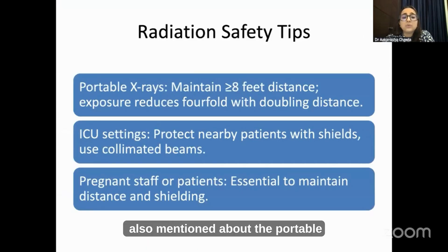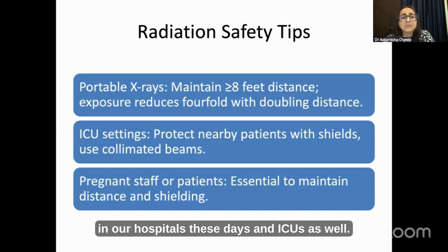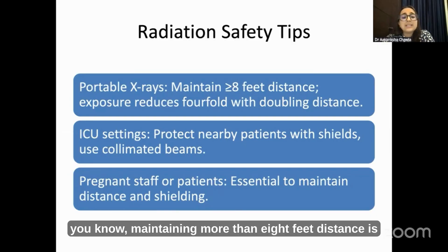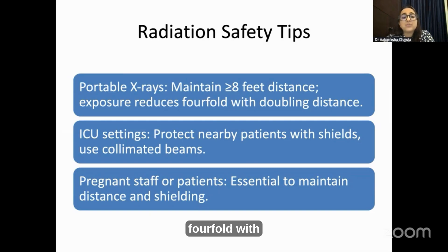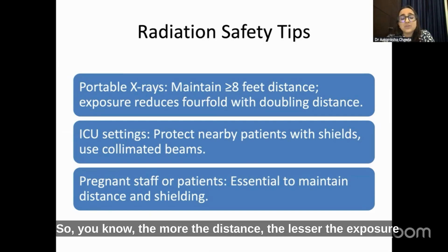Dr. K.K. Saxena also mentioned portable X-rays, which are very often used in hospitals these days, including ICUs. Maintaining more than eight feet distance is essential, and exposure reduces fourfold with doubling distance — so the more the distance, the lesser the exposure.